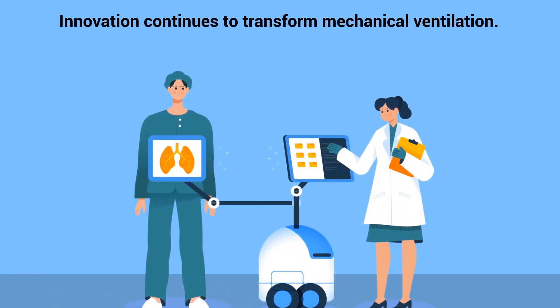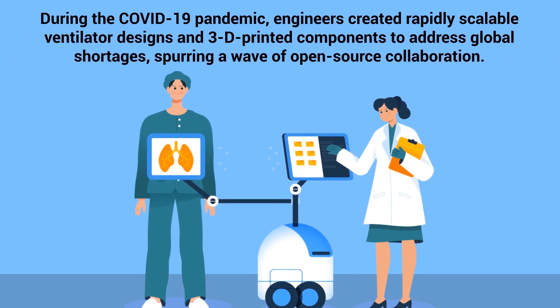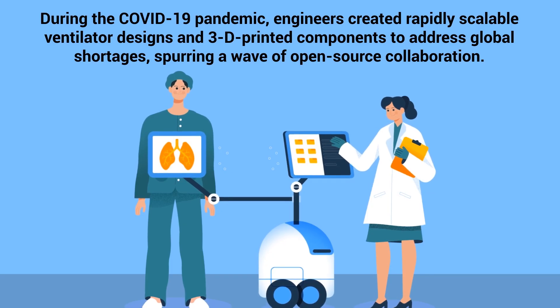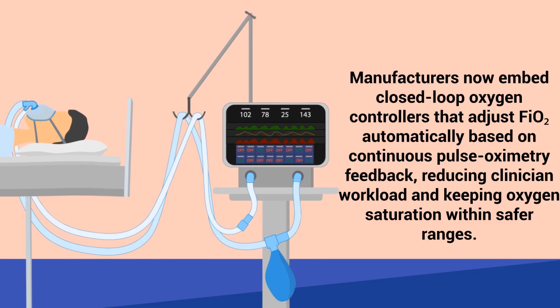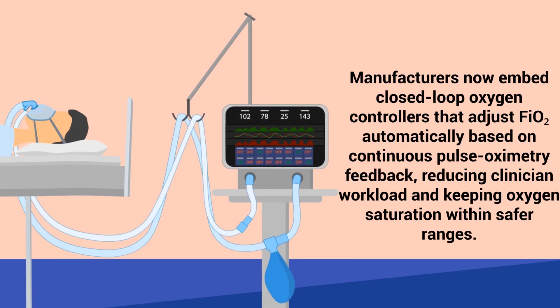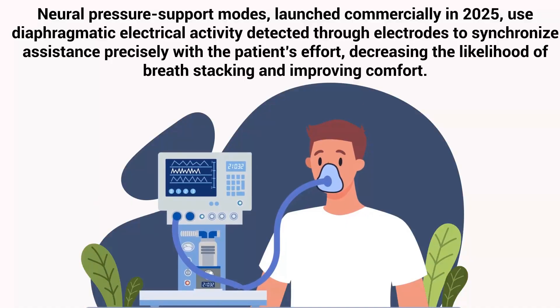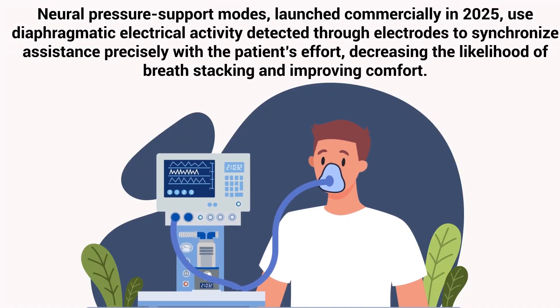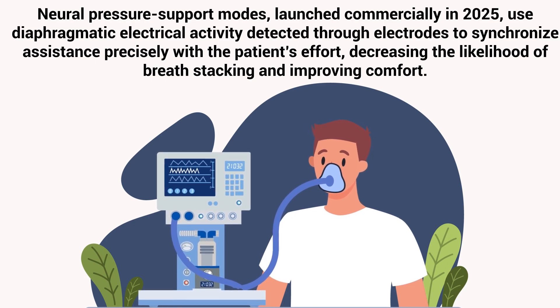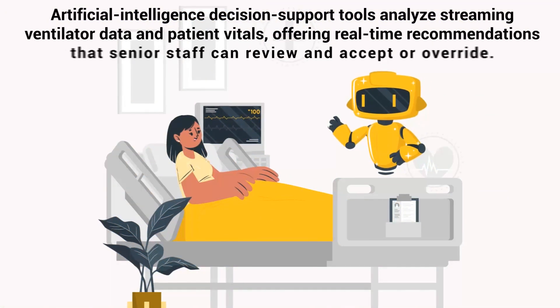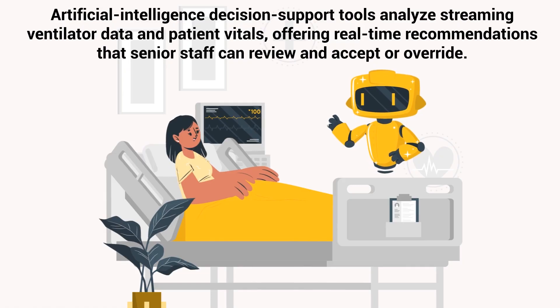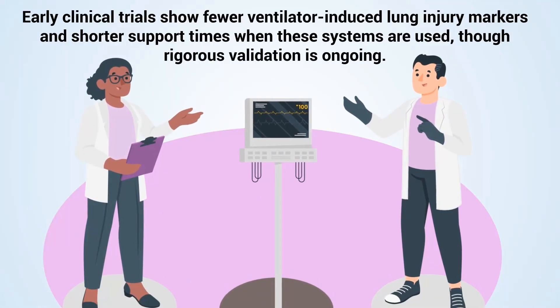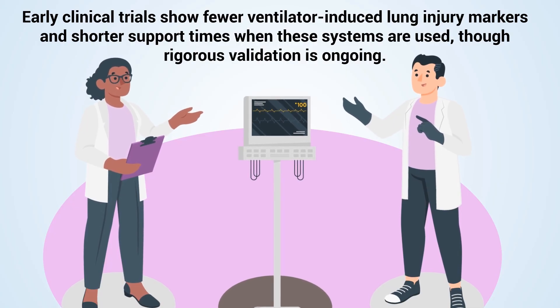Innovation continues to transform mechanical ventilation. During the COVID-19 pandemic, engineers created rapidly scalable ventilator designs and 3D-printed components to address global shortages, spurring a wave of open-source collaboration. Manufacturers now embed closed-loop oxygen controllers that adjust the FiO2 setting automatically based on continuous pulse oximetry feedback, reducing clinician workload and keeping oxygen saturation within safer ranges. Neural pressure support modes, launched commercially in 2025, use diaphragmatic electrical activity detected through electrodes to synchronize assistance precisely with the patient's effort, decreasing the likelihood of breath stacking and improving comfort. Artificial intelligence decision support tools analyze streaming ventilator data and patient vitals, offering real-time recommendations that senior staff can review and accept or override. Early clinical trials show fewer ventilator-induced lung injury markers and shorter support times when these systems are used, though rigorous validation is ongoing.